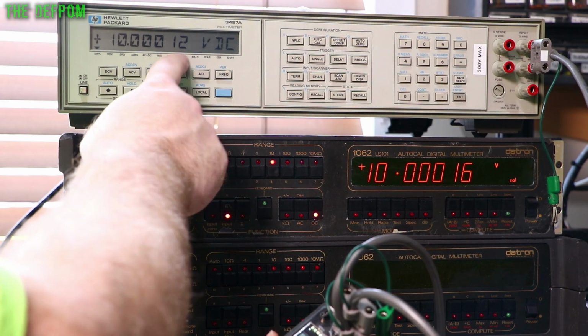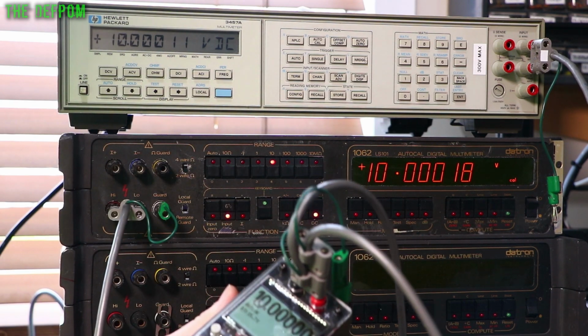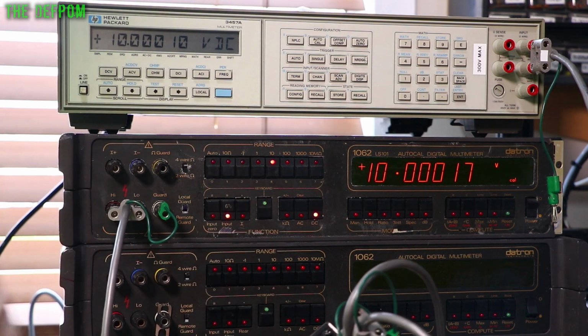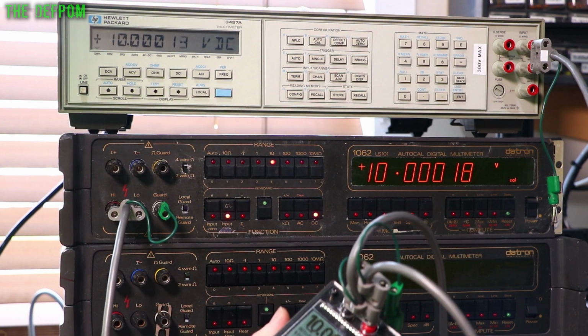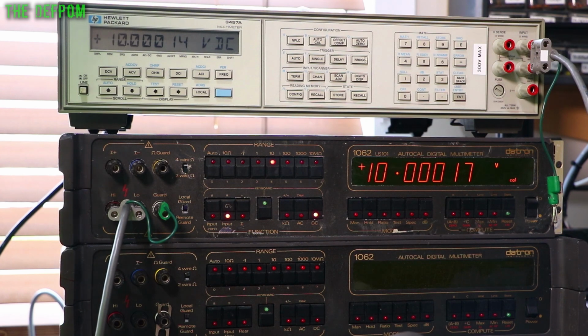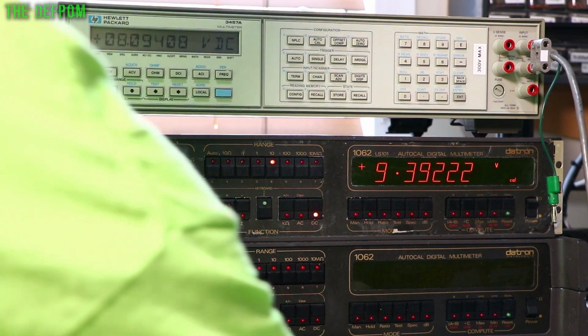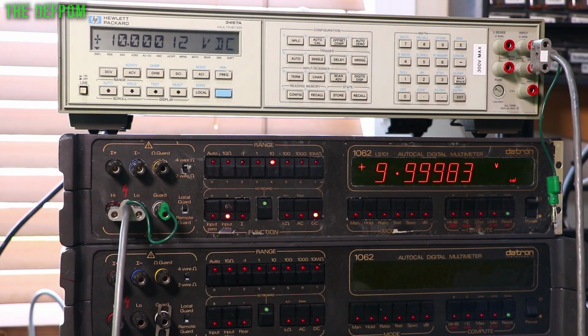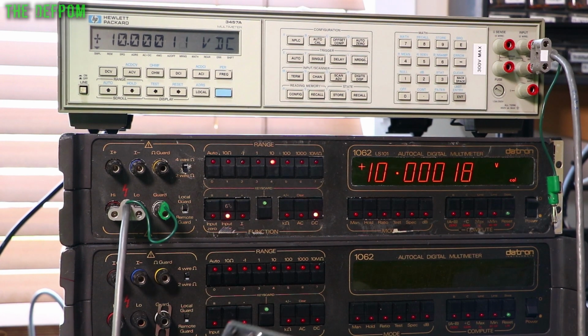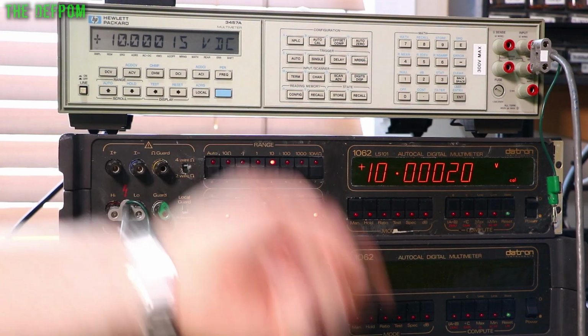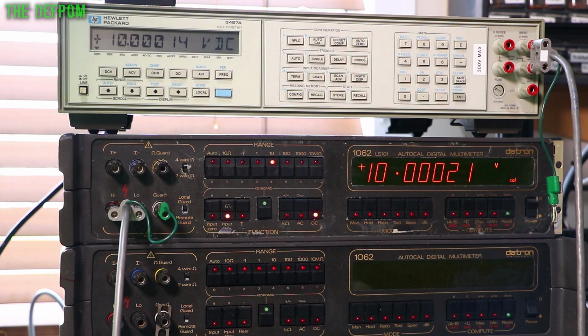So this is actually reading 10 high. So what I was actually getting at my calibrator was actually correct, because this is slightly off. I trust this thing pretty well. So I think we're actually pretty good there. I mean, it's close enough. You're talking about 10 counts pretty much being out. So I think that's good enough, really, in reality. This thing stabilises pretty quickly. It only takes like 10 seconds to be fairly stable, to be honest. It doesn't actually change that much after that point. Okay, so that basically agrees with the calibrator, so I think that's close enough.